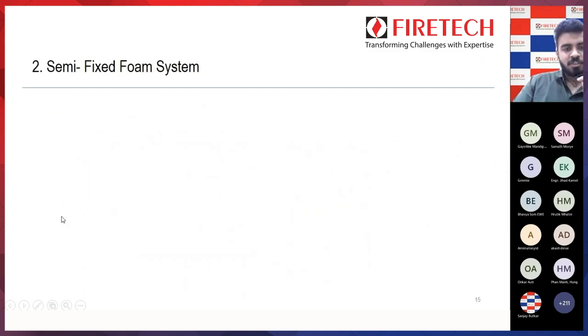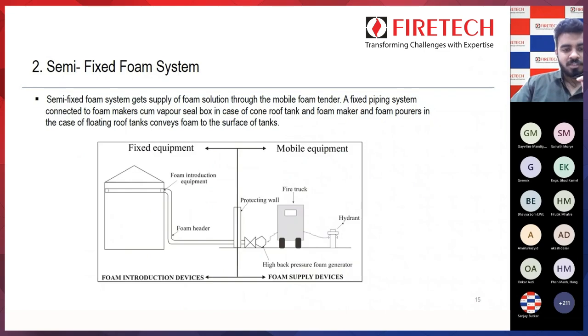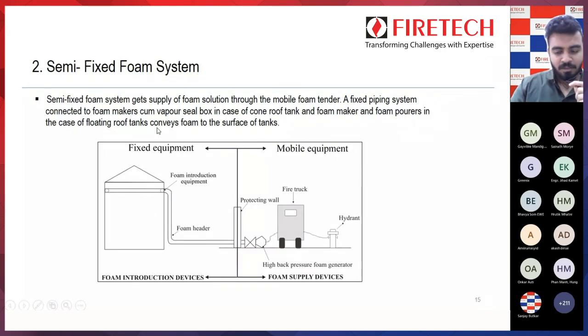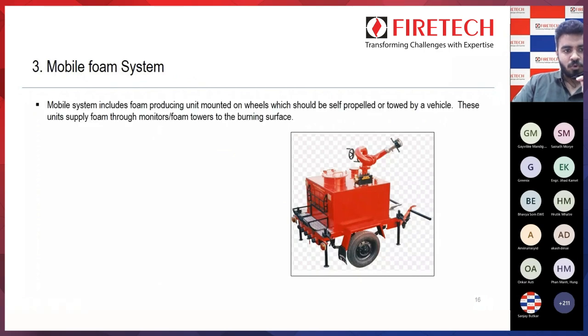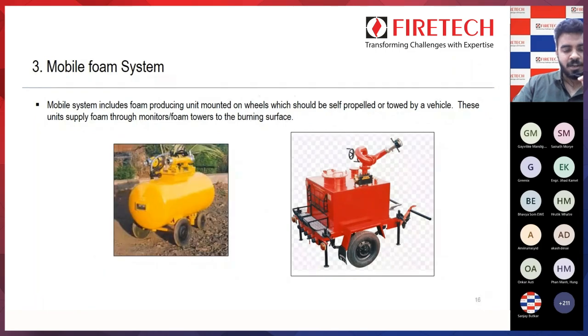Second is the semi-fixed foam system. In the semi-fixed foam system, your discharge devices are fixed, but your storage and proportioning device is movable — it is mobile equipment which is portable. You need to bring your mobile foam unit, connect it, and use it for suppression of the fire. Third is your mobile foam unit, which is a mobile system including a trolley mounted foam monitor, mobile foam unit, or water-foam monitor — all portable types you can bring to the fire scene.